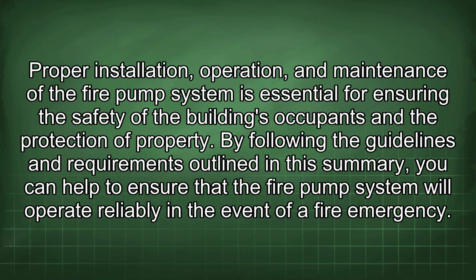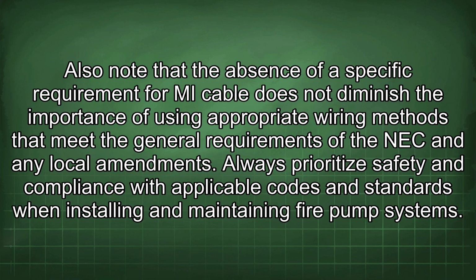By following the guidelines and requirements outlined in this summary, you can help to ensure that the fire pump system will operate reliably in the event of a fire emergency. Also note that the absence of a specific requirement for MI cable does not diminish the importance of using appropriate wiring methods that meet the general requirements of the NEC and any local amendments. Always prioritize safety and compliance with applicable codes and standards when installing and maintaining fire pump systems.